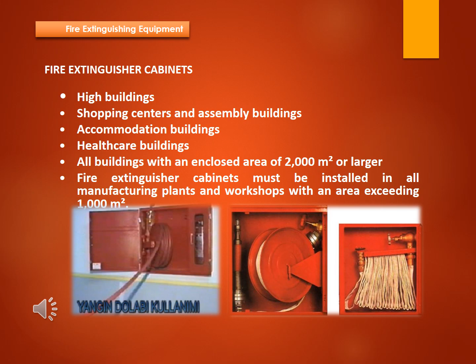There should be no more than 30 meters between fire cabinets. The cabinet shall be installed at corridor exits and stairwell landings. No fixed or movable materials should be placed in front of fire extinguisher cabinets. Required in high-rise, shopping/assembly, accommodation, healthcare buildings, all enclosed areas over 2,000 square meters, and manufacturing/workshops over 1,000 square meters.